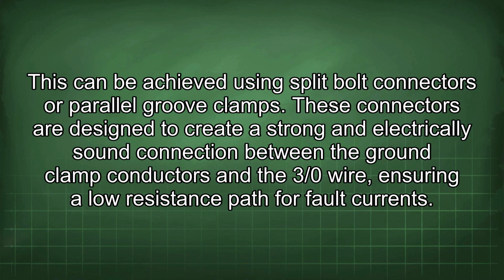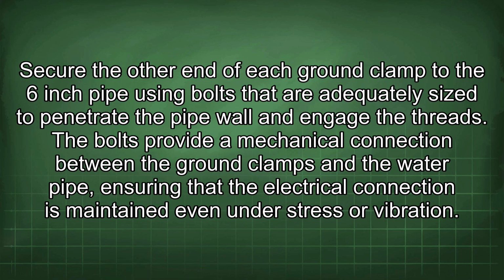These connectors are designed to create a strong and electrically sound connection between the ground clamp conductors and the 3/0 wire, ensuring a low resistance path for fault currents. Secure the other end of each ground clamp to the 6-inch pipe using bolts that are adequately sized to penetrate the pipe wall and engage the threads. The bolts provide a mechanical connection between the ground clamps and the water pipe, ensuring that the electrical connection is maintained even under stress or vibration.